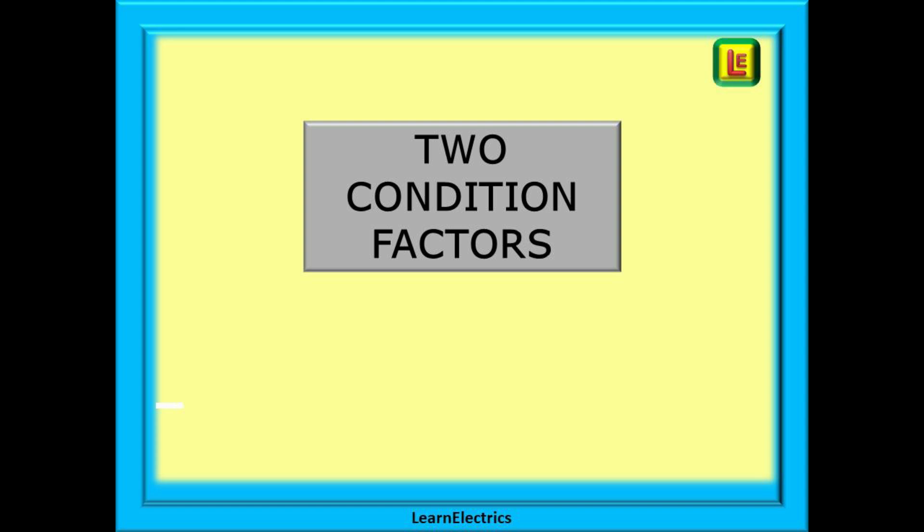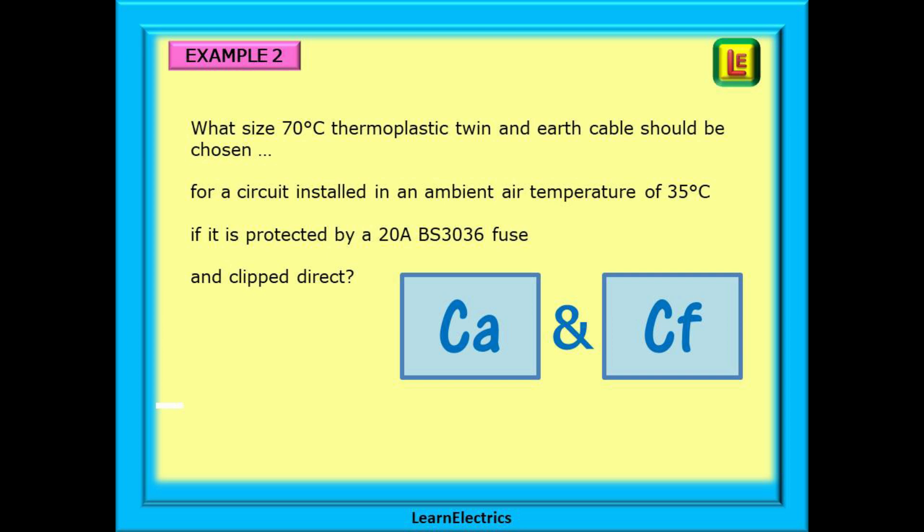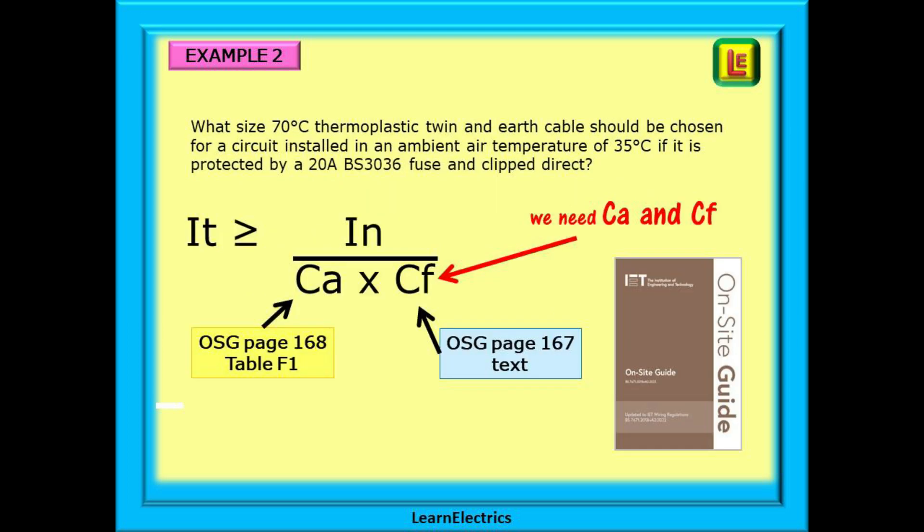Let's try two condition factors now. We are asked what size 70 degrees centigrade thermoplastic twin and earth cable should be chosen for a circuit installed in an ambient air temperature of 35 degrees centigrade if it is protected by a 20 amp BS3036 fuse and clipped direct. We've kept this the same as the last example, just added on another factor so that you can see how they build up. Now, we will need condition factors for CA and CF. We only need these two factors and we will stick with the onsite guide. Table F1 on page 168 for CA and the text at the bottom of page 167 for CF.